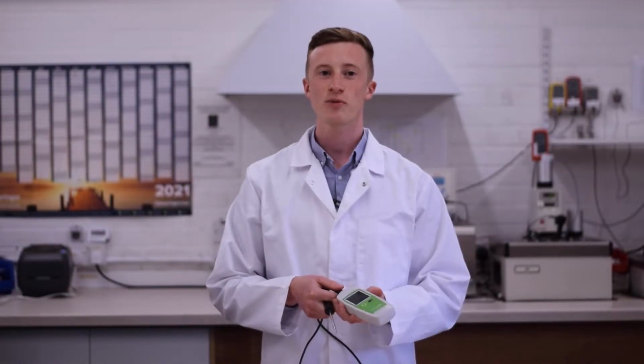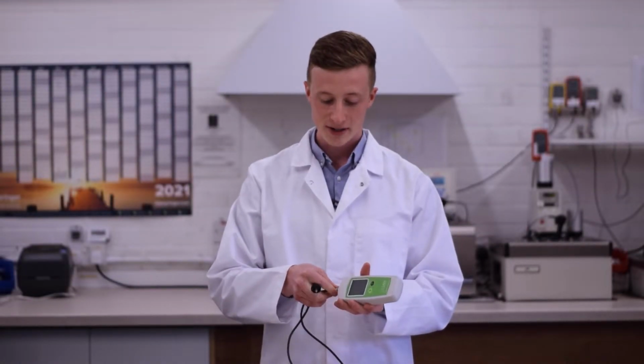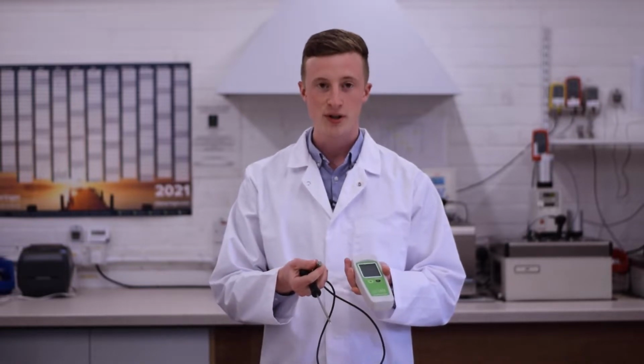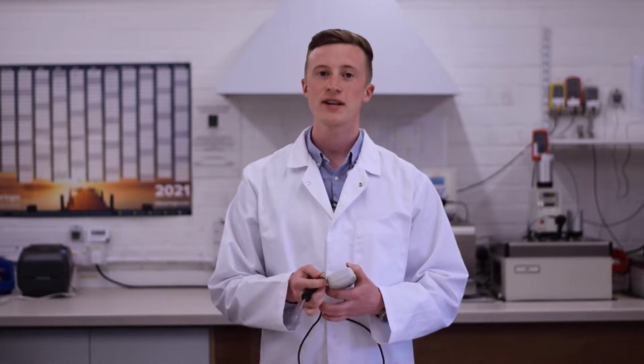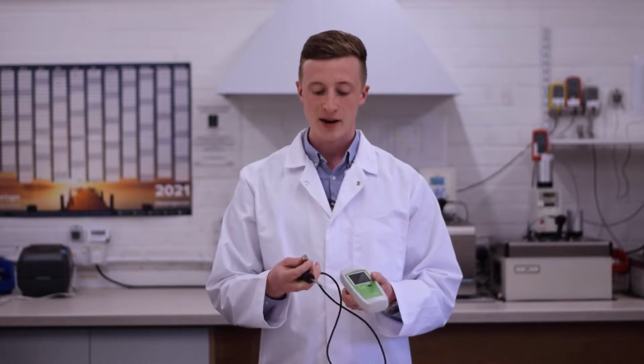Traditional detachable probe thermometers use a screw-on connector to attach the probe to the unit. Whilst this is very easy to change, it is let down by not being completely waterproof. Your thermometer needs protecting not just from water, but also steam, condensation and humidity in the air.